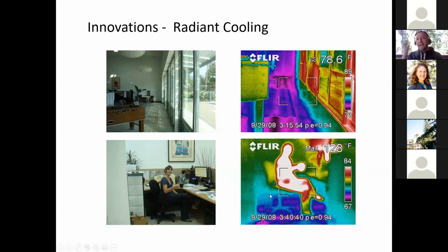So the floor is actively absorbing that energy. Radiant cooled slab floors are actually very effective at capturing direct sun. If direct sun comes into a space and hits the slab, that energy is nearly completely absorbed into the slab and the cooling system rather than dispersing into the space. So radiant cooling systems are actually quite effective at dealing with direct sun, more so than we probably thought even 5-6 years ago.